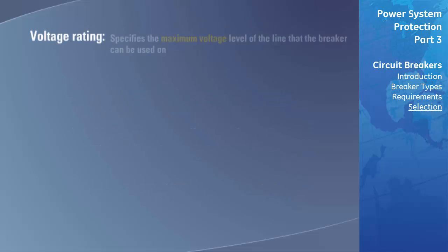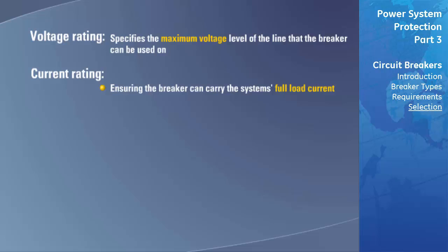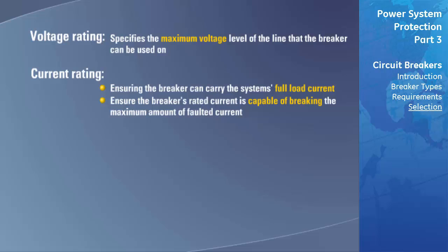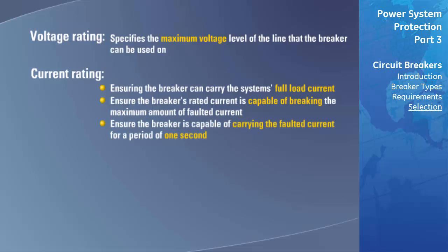The voltage rating of the breaker specifies the maximum voltage level of the line it can be used on. Three current factors must be considered: first, ensuring the breaker can carry the system's full-load current; second, ensuring the breaker's rated current is capable of breaking the maximum faulted current; and third, ensuring the breaker is capable of carrying the faulted current for a period of one second.